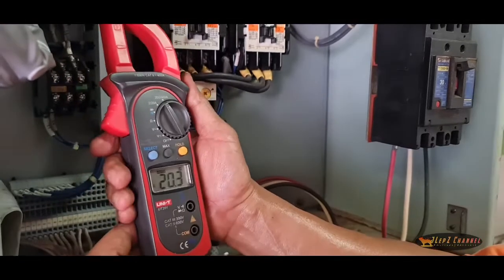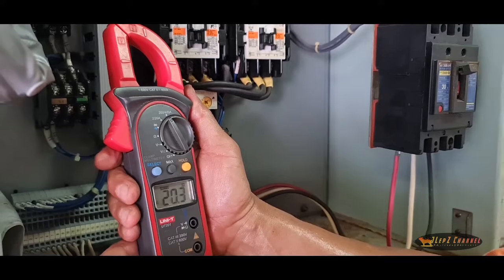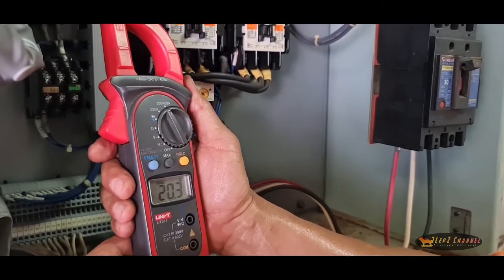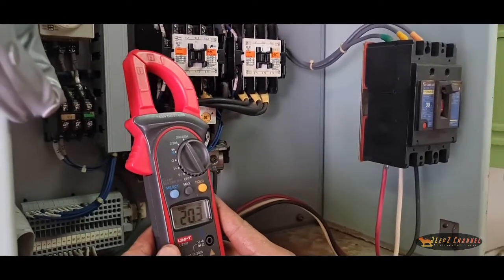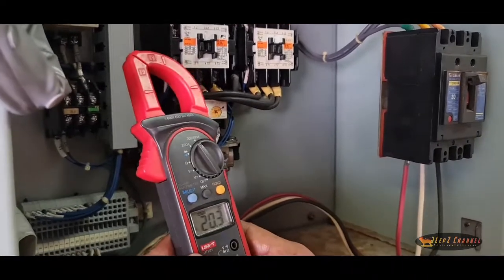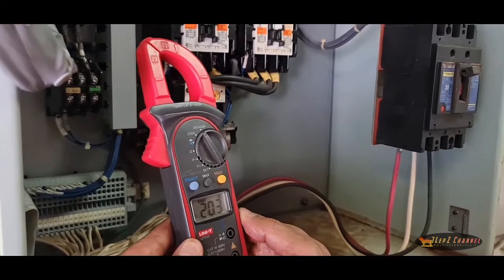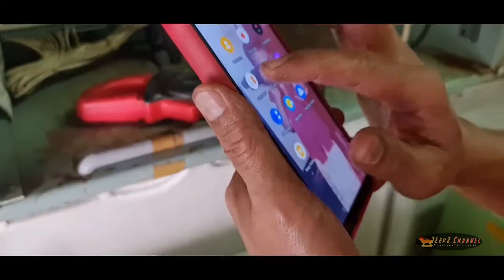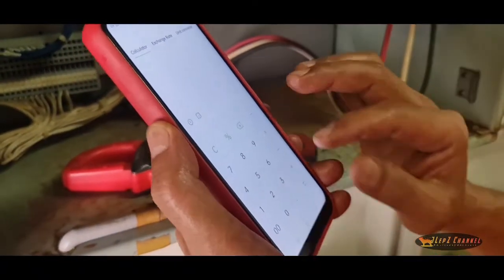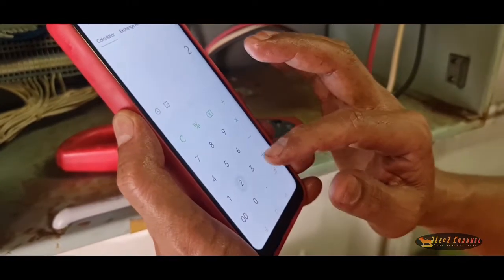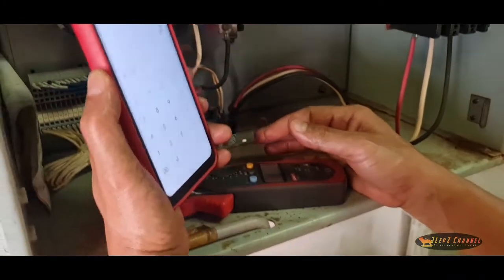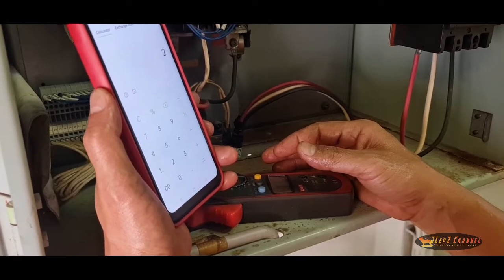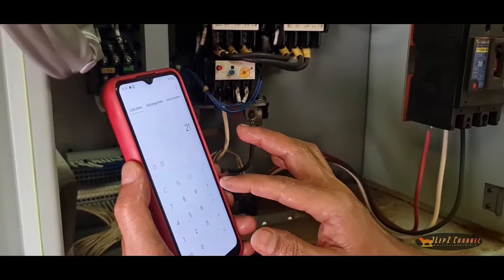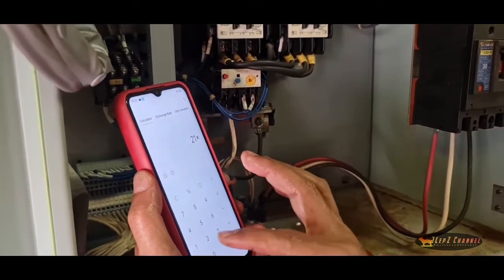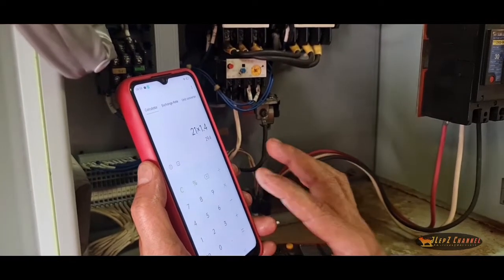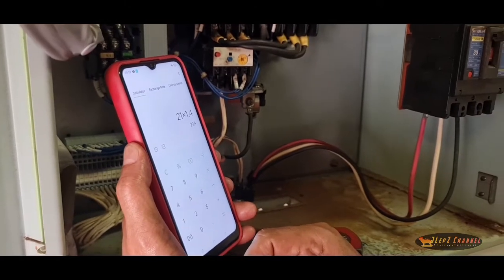Now the maximum allowable current for the overload relay setting is 140%. So 140% divided by 100 is equal to 1.4. So our previous reading, which is the highest, on line 2, is 21. So 21 times 1.4. We will choose the highest line current and multiply it by the maximum allowable setting current of the overload relay, 140%. So 21, disregarding the decimal point, times 1.4, which comes from 140% divided by 100 equals 1.4.